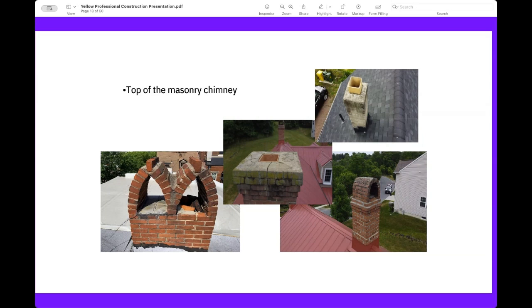This was actually somebody went in and dropped a liner into the original chimney, which was built just brick, which is not okay anymore. Okay, got it. So the first new construction I inspected had no liner in the chimney, and it was not in the 1890s that I did that inspection. It was in 2006, and there was no liner, and it was new construction. And I was like, I've got to be missing something. What am I missing here? They just didn't put it in. The agent didn't trust the builder, wasn't impressed by them, and had forced the buyer to get a home inspection. Good. They were very lucky, because even not doing a level 2 chimney inspection with a camera, just looking up, I could see that it wasn't right, and looking down that it wasn't right.